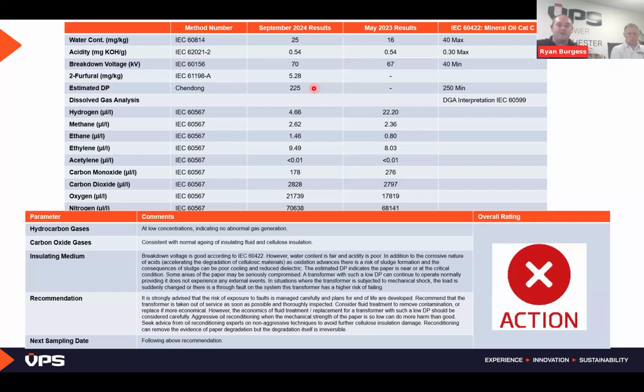So again, that reinforces the importance of knowing that if they'd just reclaimed the oil in 2023, they'd have lost all that data and they wouldn't have known that there was a potential fault with the paper itself, and that the paper has degraded. And that could have, again, as I just said, caused more damage, especially if they had decided to reclaim the oil. They potentially could have caused, especially at that point, the asset to stop working because of the paper itself being damaged beyond repair.